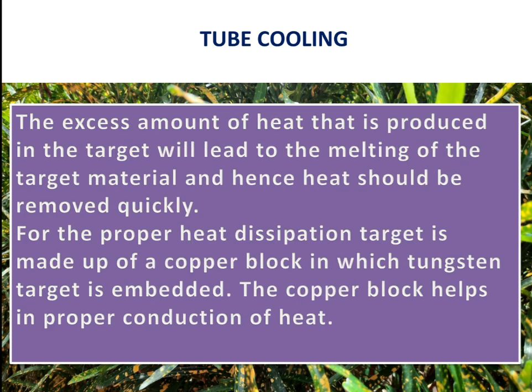There is an enormous quantity of heat generated inside the x-ray tube, and this heat must be dissipated properly to maintain proper functioning. Excess heat is produced at the target, and the x-ray tube must be equipped with a proper cooling system to remove the heat and conduct it to the external environment. Without cooling, the heat would lead to melting of the target material.